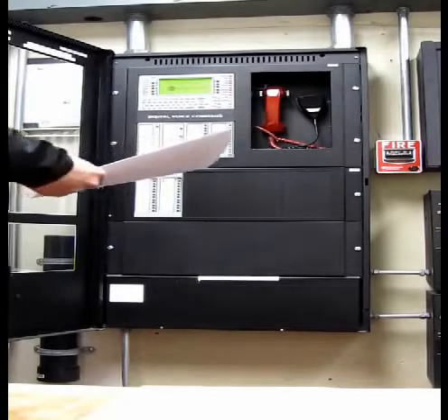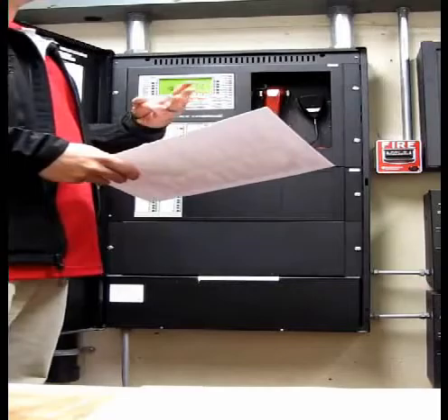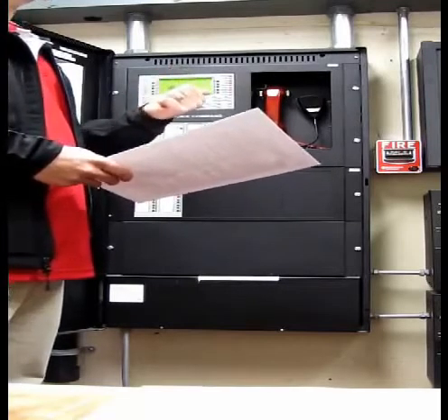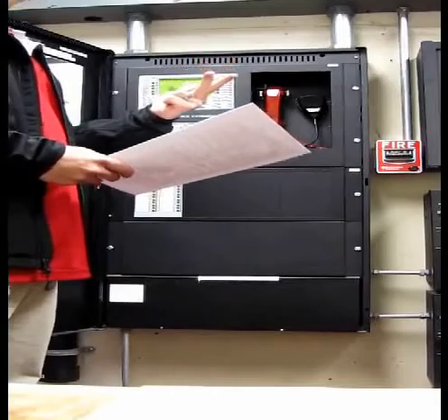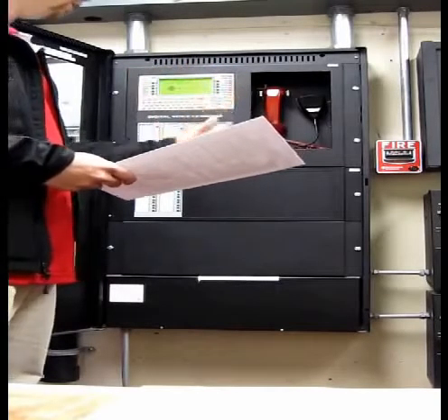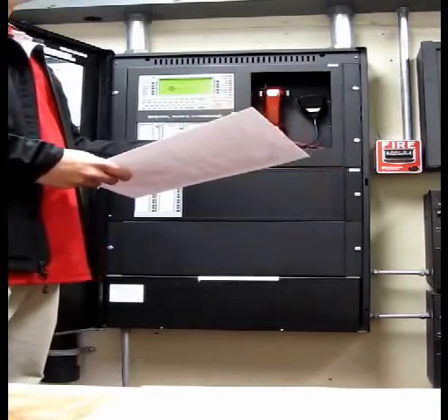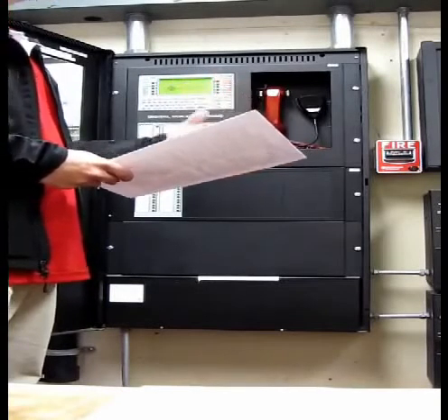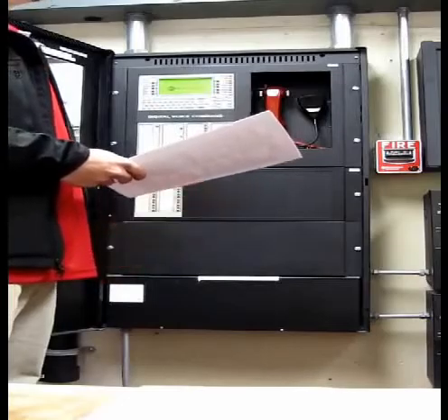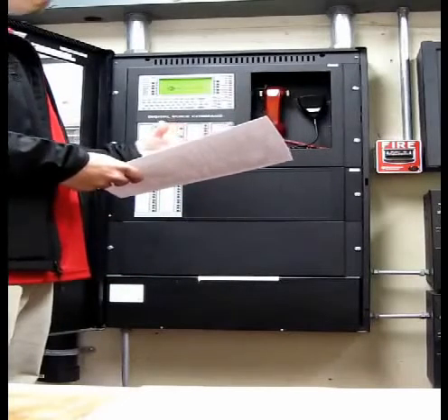Just showing you guys. So there's three types of signals that come in on a fire alarm system. You have a fire alarm, a supervisory, and a trouble condition. So we'll start with troubles. It's the easiest one. A trouble can be anything. It could be low batteries. It could be a ground fault where a wire's touching ground. It could be an open circuit. A device is dirty. A device is missing. There's numerous conditions that can cause a trouble on the panel.